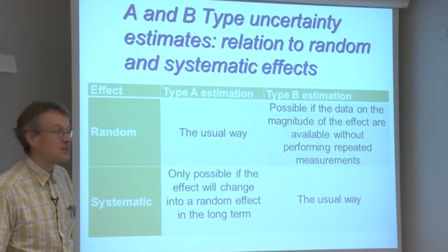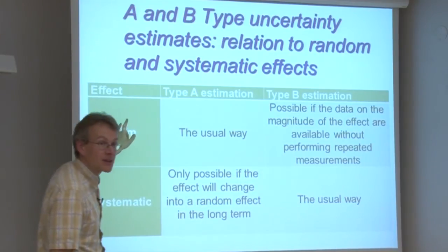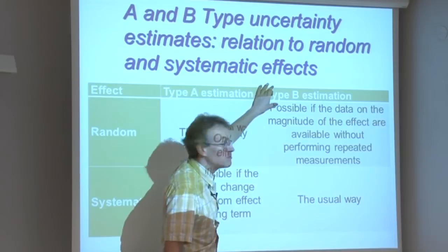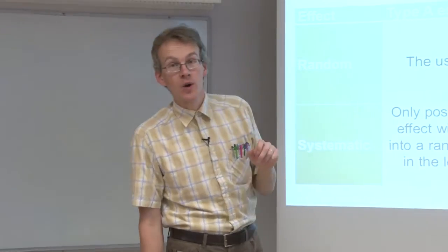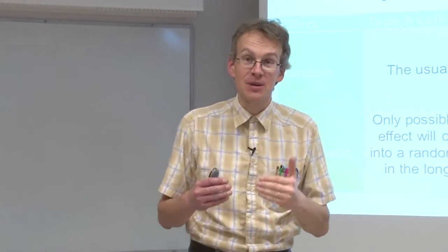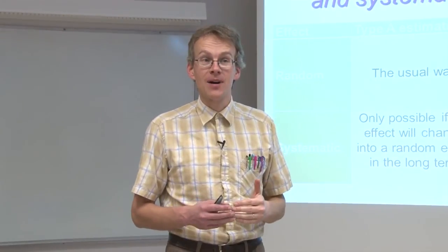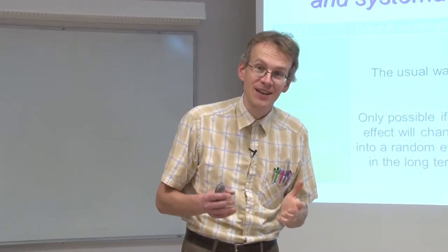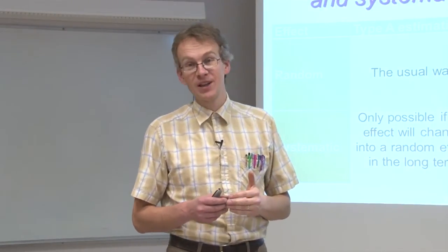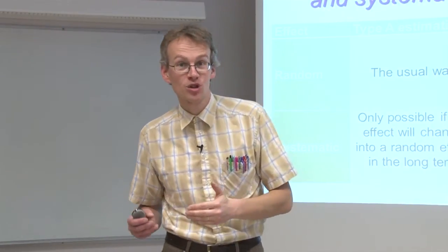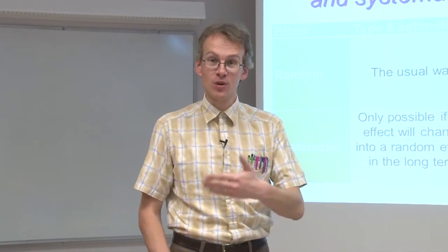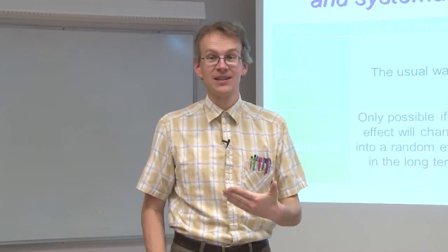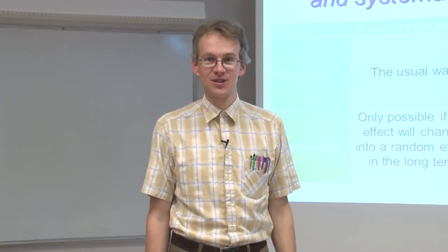Now, random effects can also sometimes be evaluated by type B estimations. And these are all those cases where we do not have the separate measurement data, but we have either some summary characteristics or we get the data from some data source which does not provide to us the original data, but only the eventual findings, the eventual uncertainty estimate.